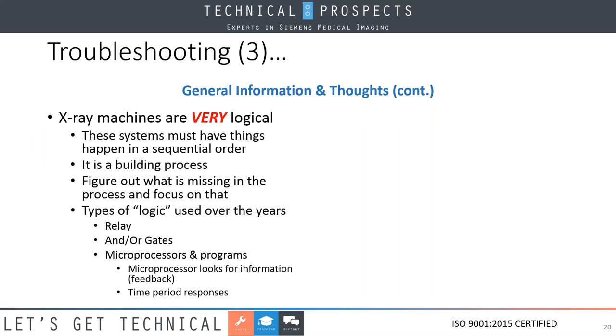I talked about the three different forms of regulation earlier, relay, and/or gates and microprocessors. The bigger thing here with microprocessors is it uses a serial. It's going around looking at all the different functions. The problem here is, and this is where our job got complicated, because it's a microprocessor, it's got embedded programming. Those responses are allowed for in a particular time frame. If it doesn't respond, the machine comes out with an error, and now we have to figure out what's going on and why things aren't responding. So what used to be simple with relay logic has now become more complex because of time responses. These can be 10 milliseconds, could be 50 milliseconds. Again, these are the kinds of things that we need to know as part of our troubleshooting.